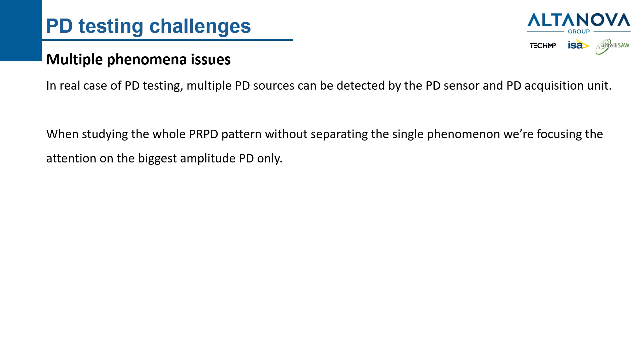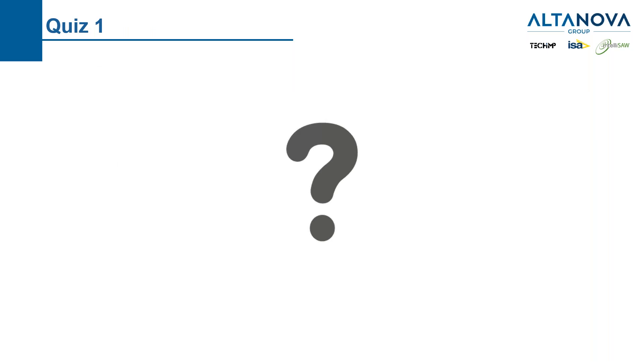The second common issue is related to multiple PD phenomena. In real PD testing, multiple PD sources can be detected simultaneously by the PD sensor and acquisition unit. When studying the whole PRPD pattern without separating individual phenomena, we focus only on the highest-amplitude partial discharges and miss the lower-amplitude ones.